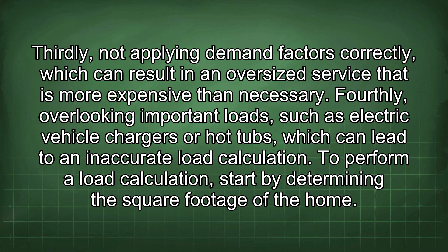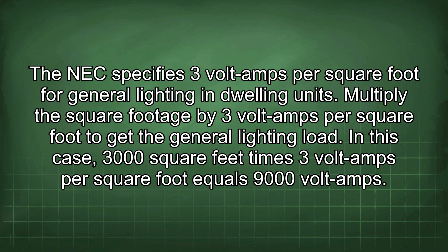Next, calculate the general lighting load. The NEC specifies 3 volt amps per square foot for general lighting in dwelling units. Multiply the square footage by 3 volt amps per square foot to get the general lighting load. In this case, 3,000 square feet times 3 volt amps per square foot equals 9,000 volt amps.